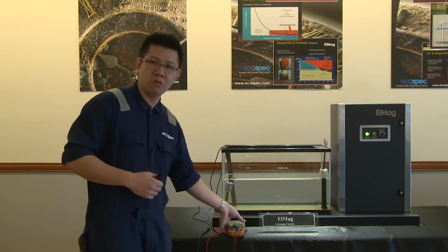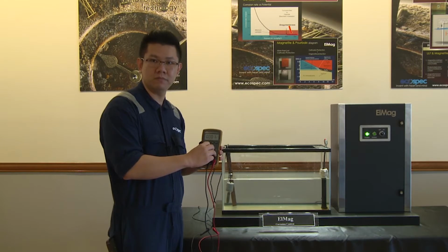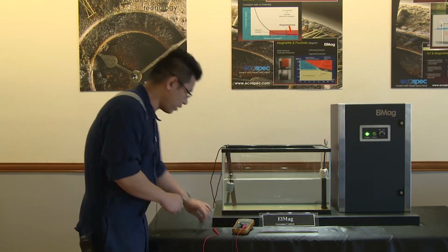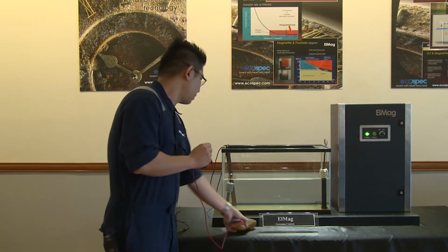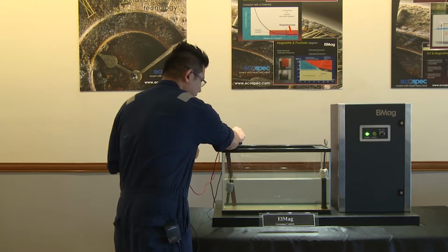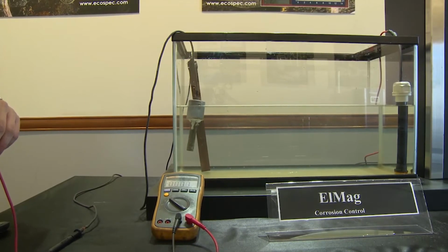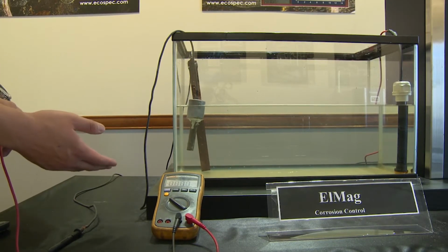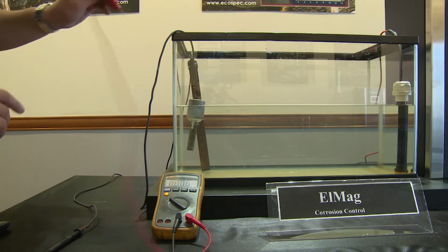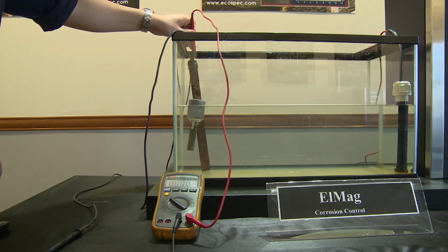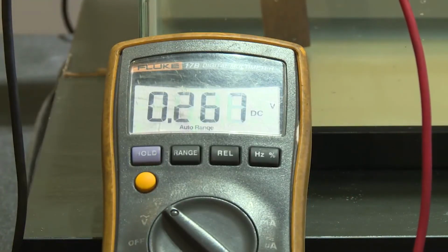For the measurements, we can use the multimeter, right, as you see here, and then we turn to the DC mode, okay? And the negative side, we connect to the reference cell, whereas the positive side, you can touch on the test piece, or you can touch on the terminals that are connected with the test piece. Okay, let's go. So before we start, we can see the multimeter in DC mode now, the value is almost 0. So the positive terminal of the multimeter should touch on the metal piece. So now we touch on the metal piece, we will see the reading become 250 to 260 millivolt, right?